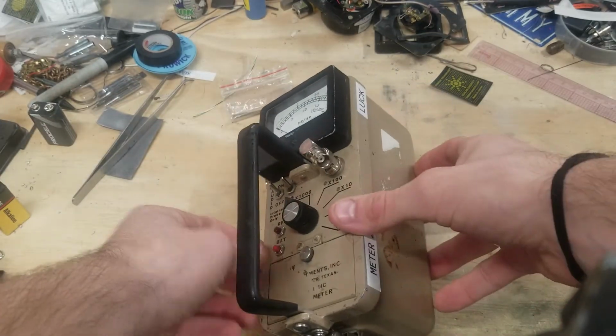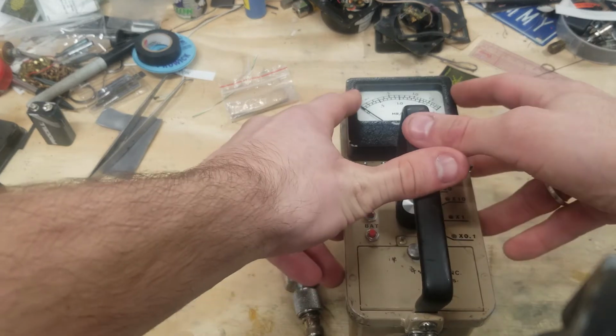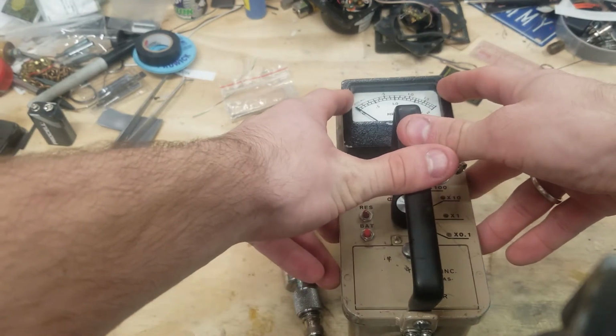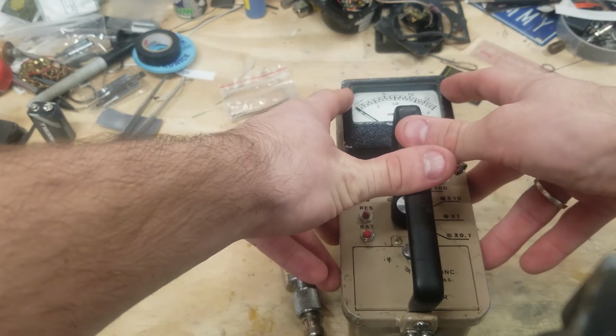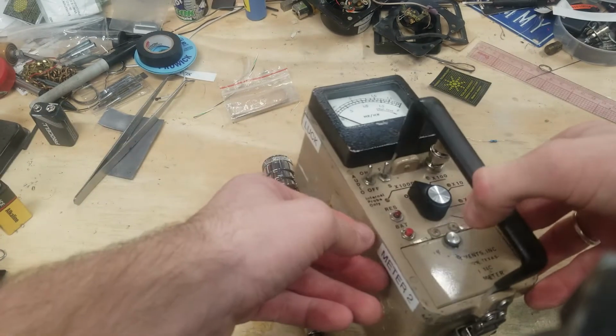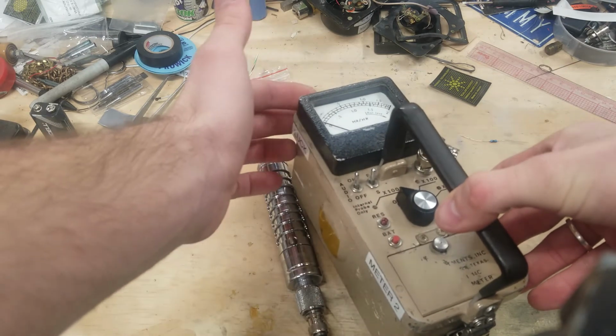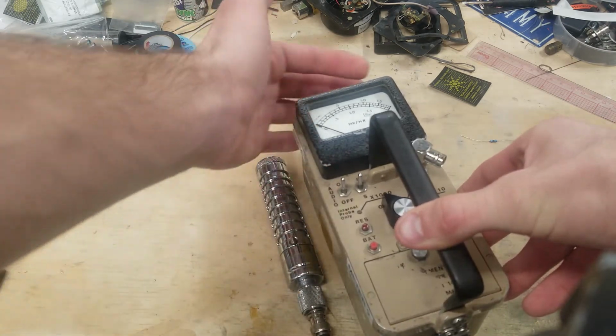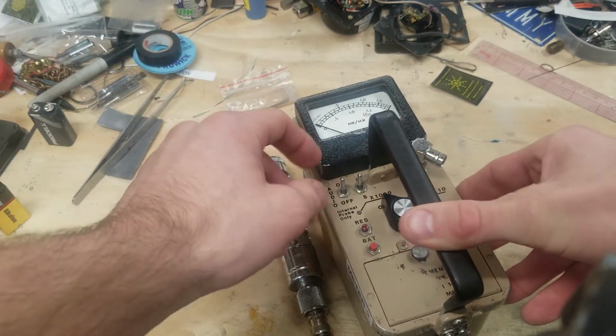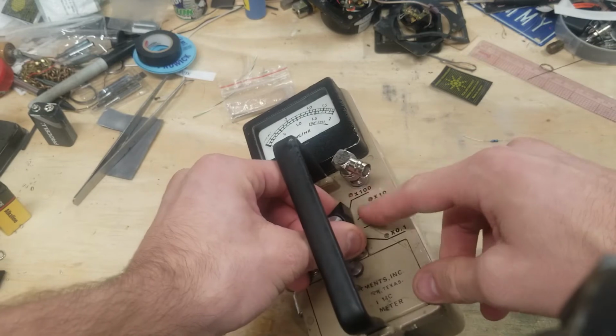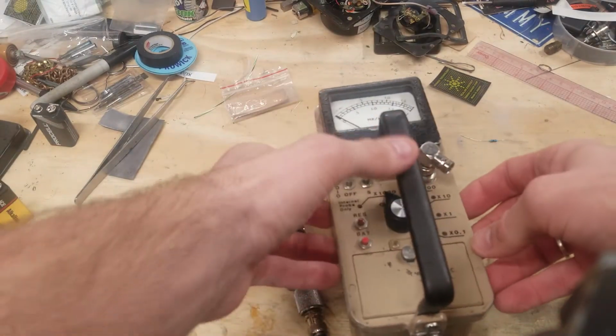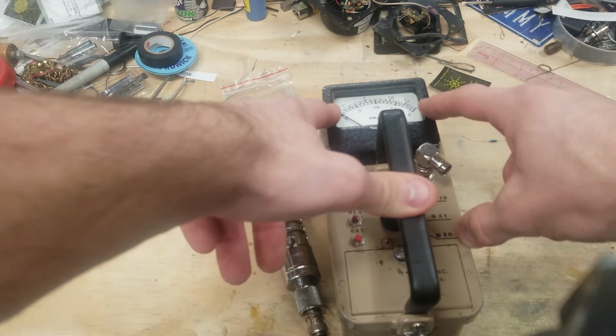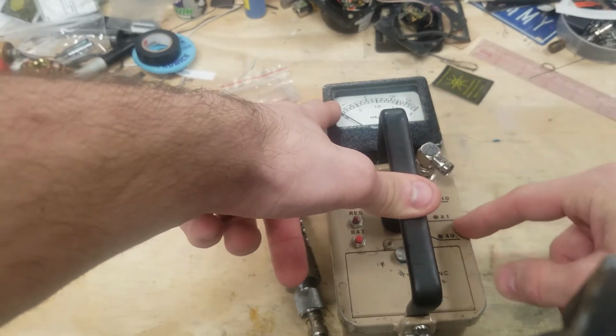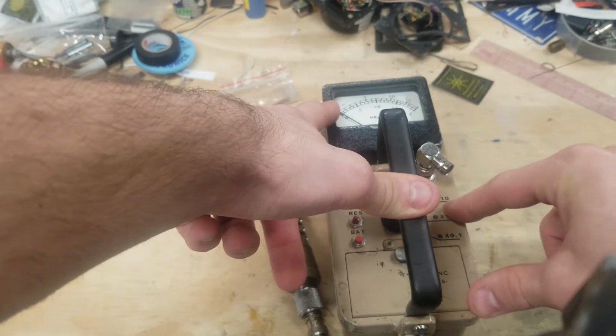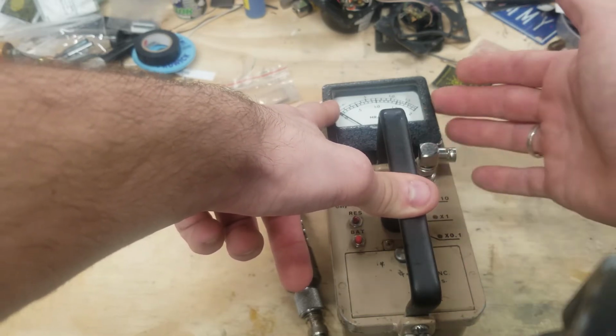This meter is a relatively good design and packs a nice high-range tube, in this case set up to go between 0 and 1.5 mR an hour. Oh, I apologize. The tube can only be used on the times 1000 scale. So actually, it's between 0 and 1.5 R an hour, while everything else can be used on all the other scales. So you can read the needle face from 0 to 2 mR on the times 1, 0 to 20 mR on the times 10, or 0 to 200 mR on the times 100.